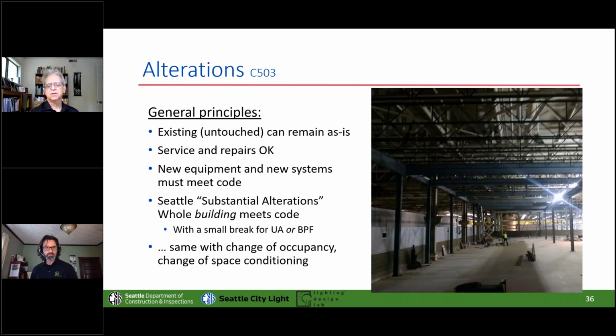Okay, just to get into alterations for a minute here. In general, stuff that you put into your building and met code back in 1947 or whatever could just stay the way it is. Our boiler inspectors say that they've got some boilers they check annually that are 85 years old now. You can repair stuff, you can service it, but if you're taking out the old one finally, dragging all the asbestos with it, and putting in a new one, it's got to meet code.